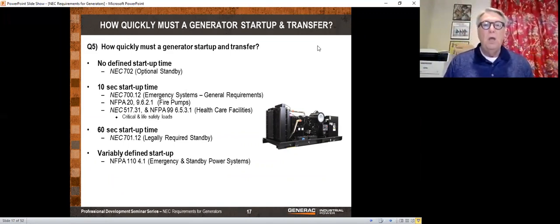Now, let me mention one thing with regard to the 10-second startup time. All generators cannot start up in 10 seconds. Typically, a diesel generator is going to be able to start up in 10 seconds. Natural gas, all the smaller ones can, but the bigger natural gas generators many times cannot start up in 10 seconds. And so you need to make sure that you talk to the manufacturer if you're going to use one of these in an emergency application. I can tell you this, that all generators that Generac makes, whether natural gas or diesel, not only will they start in 10 seconds, but we will guarantee that we can start 2 of them and parallel them in 10 seconds.